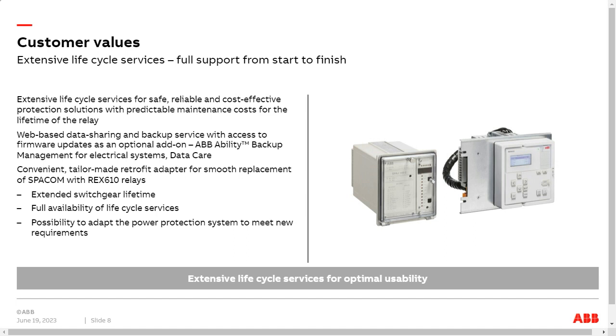Also, for example, if you happen to have some SPACOM relays, if you take a look at the picture there to the left, it's very convenient to update it to REX610, and to make it even simpler, we have this adapter kit. So it's very easy to move the wiring over to these connectors we can see on the plate around the REX610. So it's a very swift replacement of the device on site. And then of course there are also some templates and instructions on how to migrate the configuration from the older one to the newer REX610.